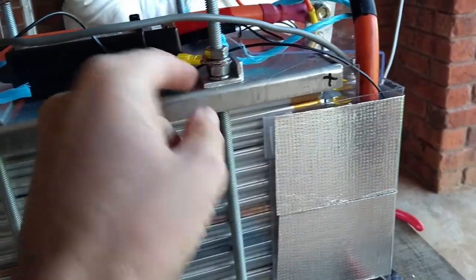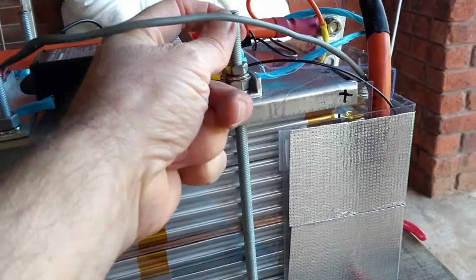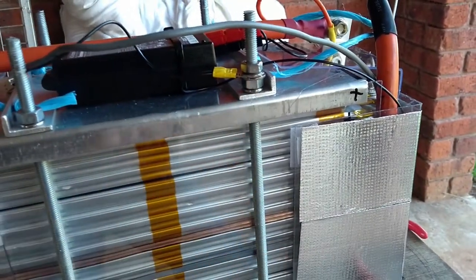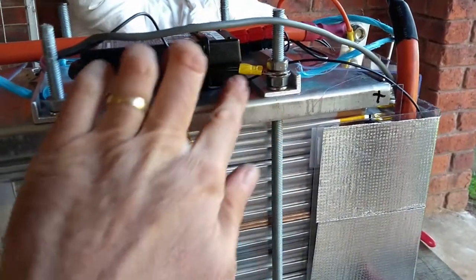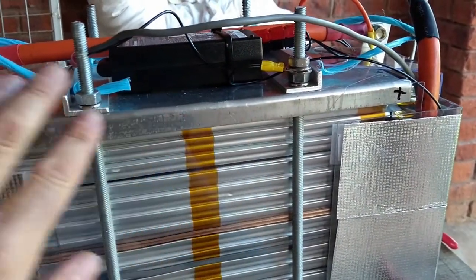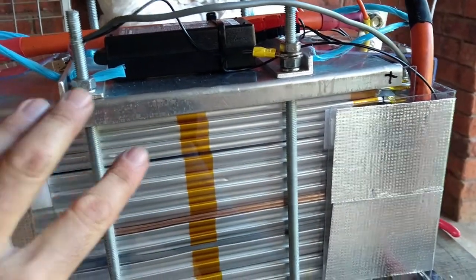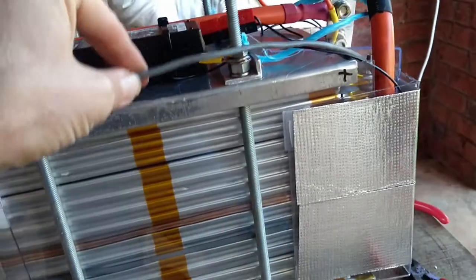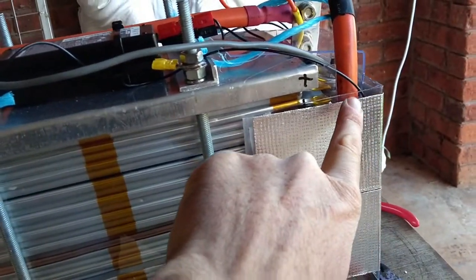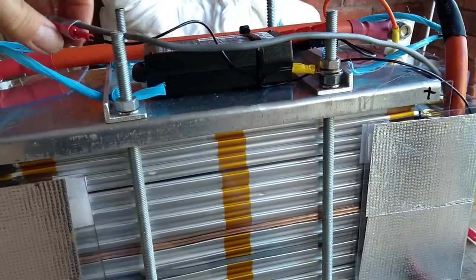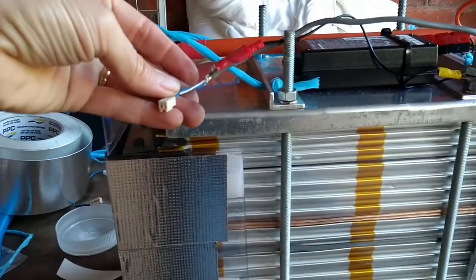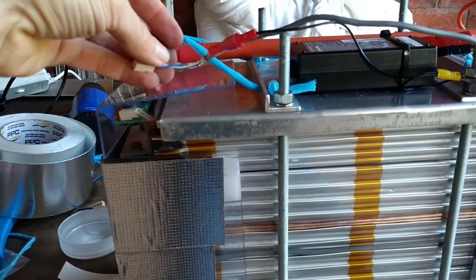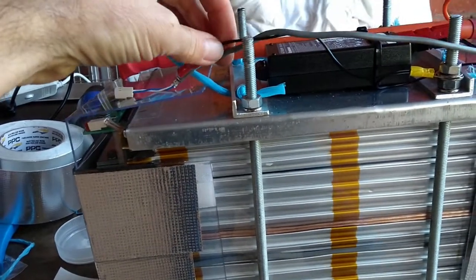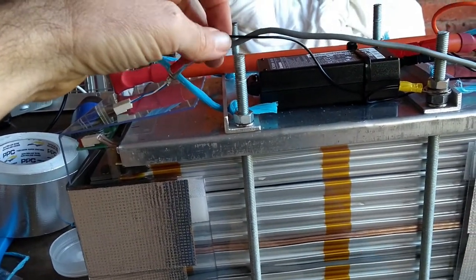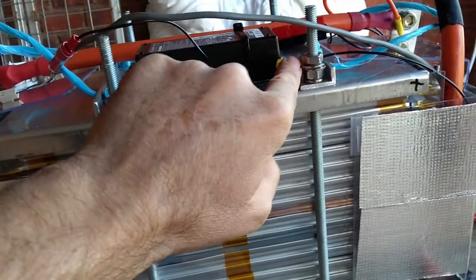The earthing wire comes up here and is attached to the side of the battery module, the frame of the battery module. The other shielded cable here is from this end and will plug into where it comes into the battery box itself. That's also earthed - the shield is earthed on one end back to the frame here.